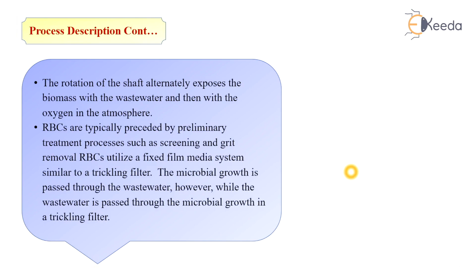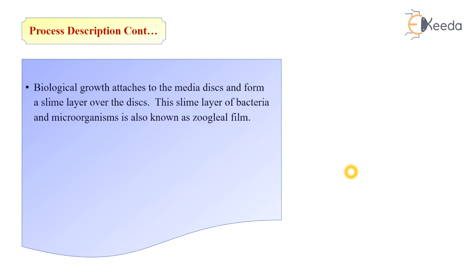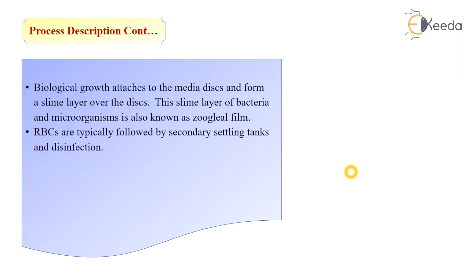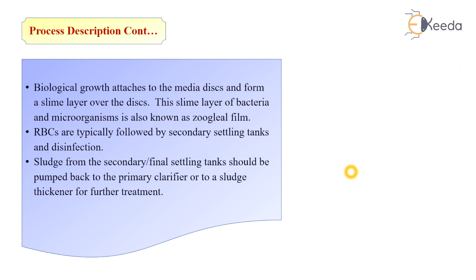The biological growth attaches to the media disc and forms a slime layer over the disc, similar to a trickling filter. This slime layer of bacteria and microorganisms is also known as zoogloeal film. The rotation of the shaft alternately exposes the biomass to the wastewater and then to oxygen in the atmosphere. RBCs are typically preceded by preliminary treatment such as screening and grit removal, and followed by a secondary settling tank and disinfection. Sludge from the secondary settling tank should be pumped back to the primary clarifier or to a sludge thickener for further treatment.